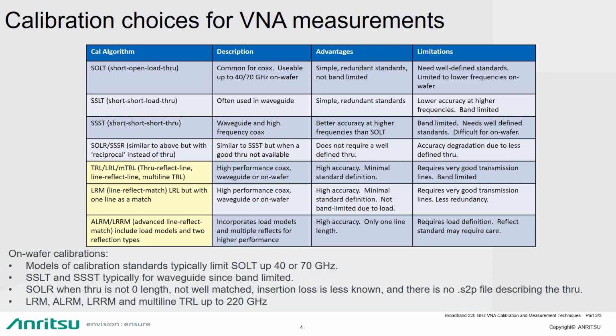So then we get into the other group of calibrations that are often used in on-wafer situations, and there's different reasons for using the different types. Starting off with TRL, LRL, and multi-line LRL. The use of lines are what define the accuracy of the calibration, and so it's going to be a fairly good alternative to having well-defined standards, because as long as you have a good connection to a line that represents the characteristic impedance of the media, then you will usually end up with some fairly good results.